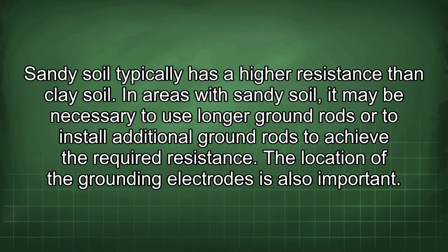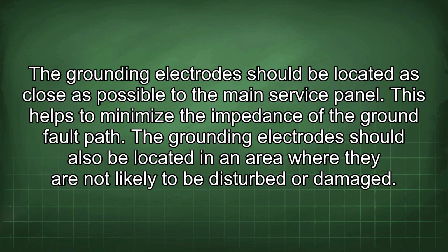The location of the grounding electrodes is also important. The grounding electrode should be located as close as possible to the main service panel. This helps to minimize the impedance of the ground fault path. The grounding electrode should also be located in an area where they are not likely to be disturbed or damaged.